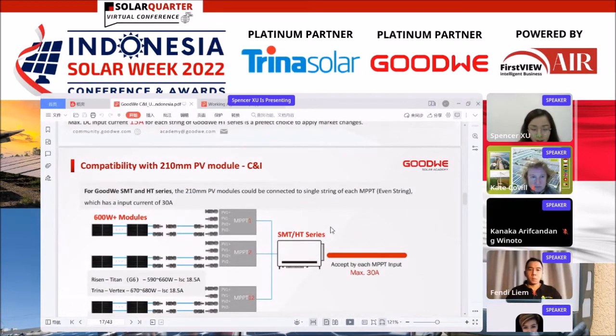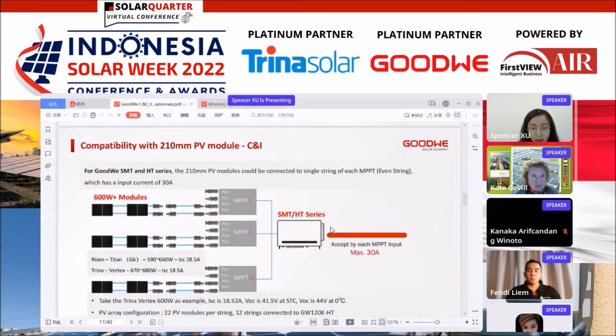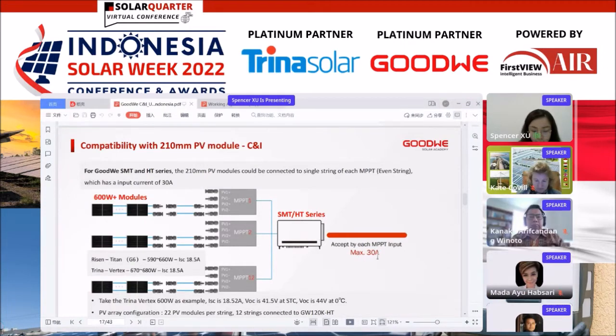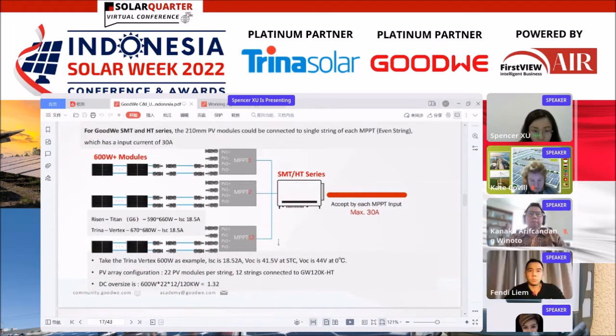While for the 210 millimeter PV modules, for the commercial and industrial scenarios, we offer single string connection for each MPPT, so that we can have a maximum input current of 30 ampere. So here we take Trina Vertex 600 watt and GoodWe 120 kilowatt HT as an example. We can see the short circuit current is 18.52 and the open circuit voltage is 41.5 at STC. And after some calculation, we found that we can have 22 PV modules per string and 12 strings are connected. And we can find that the DC oversizing still can reach 132%.